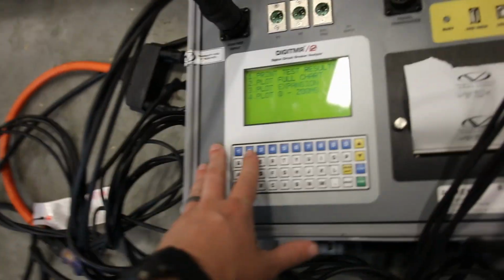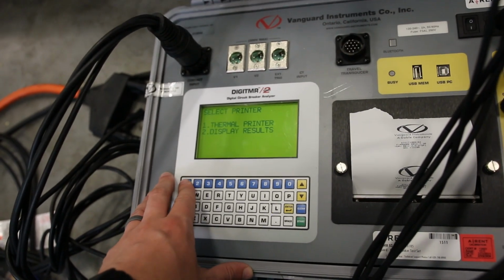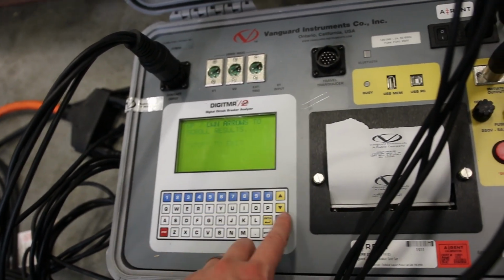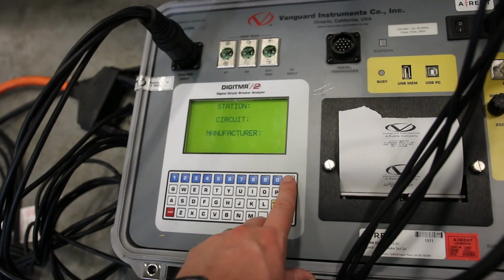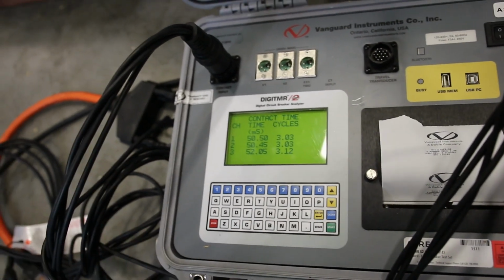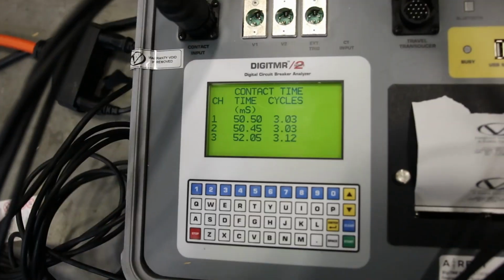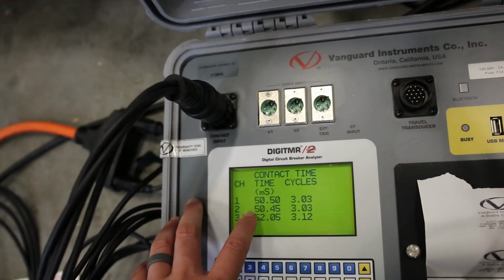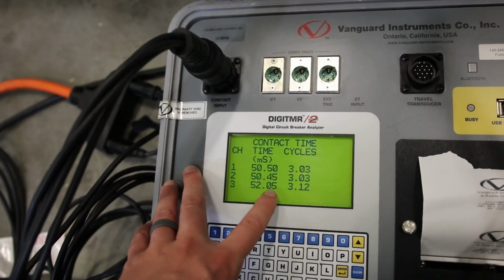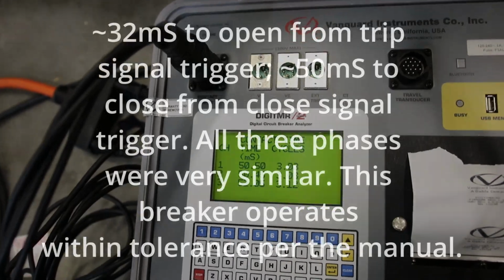Which should be get results. Because we're doing 1 test at a time. You can set this up to do a bunch of them, but we're only gonna do 1 test at a time. This one operated in about 3 cycles, so 50 milliseconds, and 52.05. So that's right on the cusp of being in tolerance.